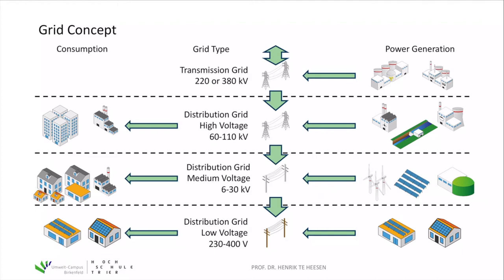There are four different grid levels in the European grid and mainly all over the world. The highest grid level is the transmission grid with a voltage of 220 or 380 kilovolts. This grid level is used to exchange electricity with other grids of other countries or other regions. Power generation comes from very large power plants like nuclear power plants or very large lignite or hard coal power plants with capacity on a gigawatt level, feeding their electric power directly to the transmission grid.